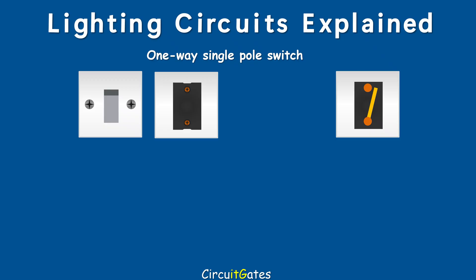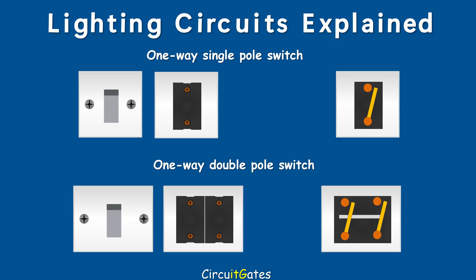The term pole is usually associated with how many electrical conductors the one-way switch, the two-way switch, and the intermediate switch control. For example, this one-way switch is a single-pole switch because when operated, only one conductor is opened or closed. Another one-way switch here is a double-pole switch because when operated, two conductors are opened or closed at the same time.